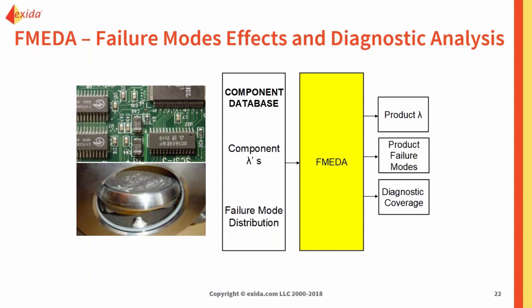We do this because, just like the safe and dangerous, detected and undetected failures we talked about before, different failure modes can be dangerous in one FMEDA application or safe in another. For example, a ball valve can be operated in both open to trip or close on trip application, where a failure might be dangerous in one and safe in the other. Along with the application and the operation, if it's severe service or clean, we look at six different environmental profiles, going everywhere from climate controlled the whole way to offshore, subsea, and process wetted with severe service, and anything in between.